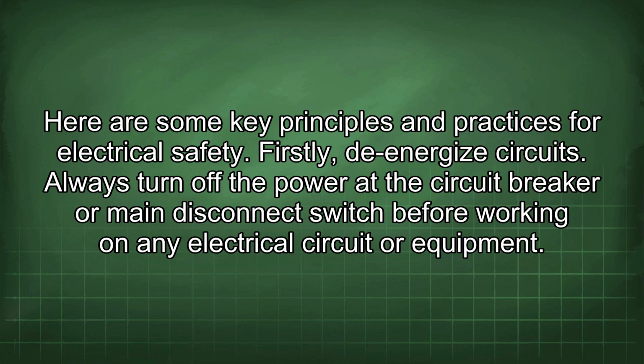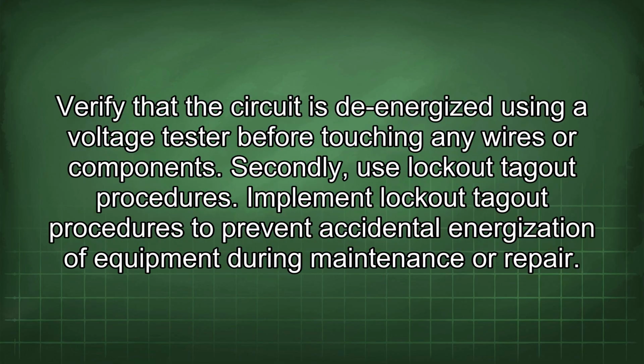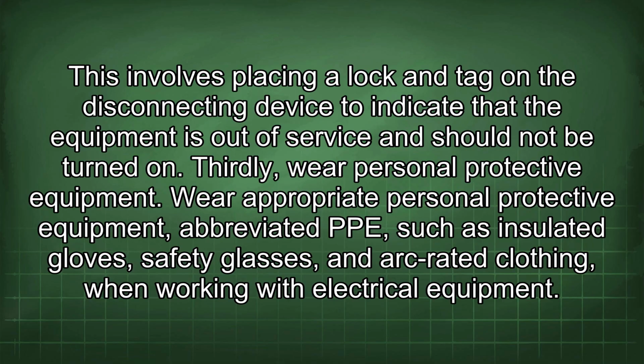Firstly, de-energize circuits. Always turn off the power at the circuit breaker or main disconnect switch before working on any electrical circuit or equipment. Verify that the circuit is de-energized using a voltage tester before touching any wires or components. Secondly, use lockout-tagout procedures. Implement lockout-tagout procedures to prevent accidental energization of equipment during maintenance or repair. This involves placing a lock and tag on the disconnecting device to indicate that the equipment is out of service and should not be turned on.